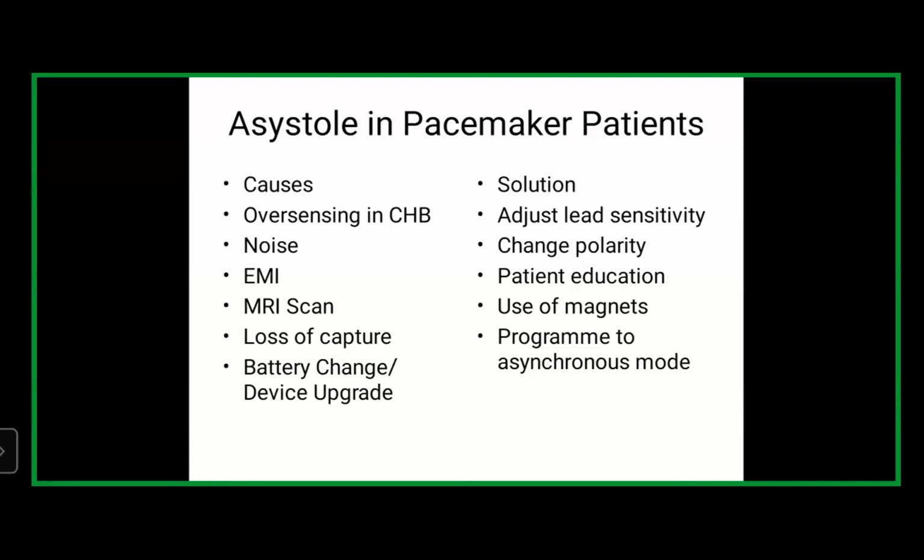Also, primarily do your check before the device change to confirm the patient has an intrinsic rhythm. And if not, that would help to plan the strategy for changing the battery or upgrading the device, whichever the case.